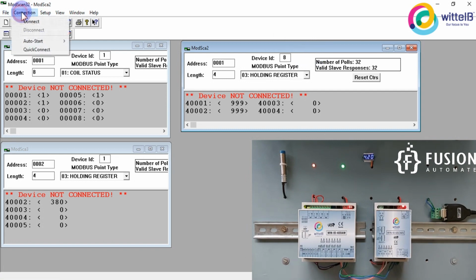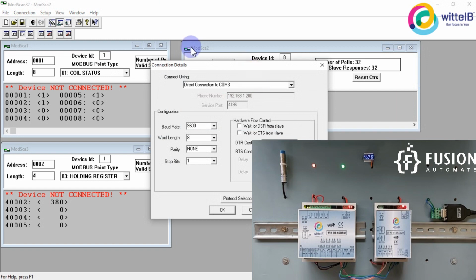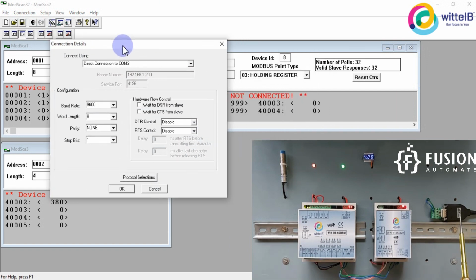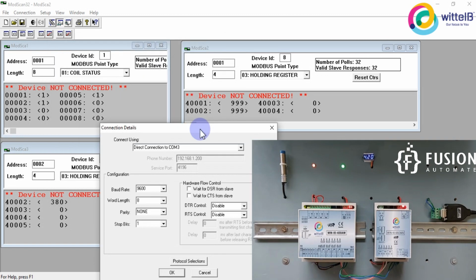Now if you go to connection and click on connect, you will see this ATC converter is connected with my laptop on the COM3 port, so that is why I have selected the COM3 port here. Both Modbus IO cards have a common configuration: baud rate 9600, word length 8, parity none, and stop bit 1. I have filled in the common settings here, but the difference between these two cards is their slave ID. This Modbus IO card has slave ID 1, or you can say device ID 1, and this one has slave ID 8.